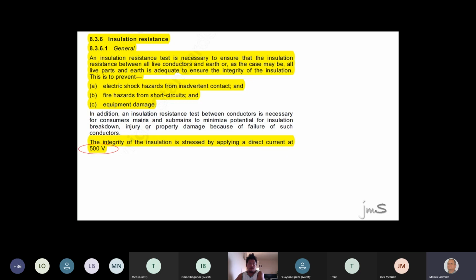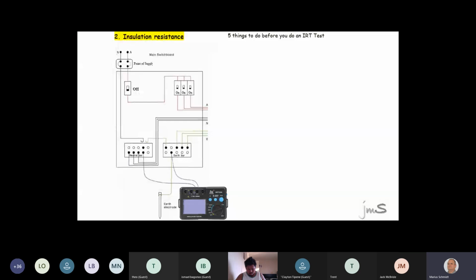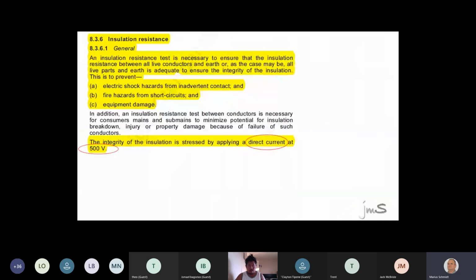Right, guys, you would have heard, oh, it must be double 230 volts, or it must be this, or must be that. The most correct answer is this. Come back. Have you ever heard about peak voltage? What's peak voltage? What's RMS voltage? RMS is 230. Divided by 0.707, you get 325 volts. So your test voltage must be greater than 325. Got it? And that's why we choose 500.